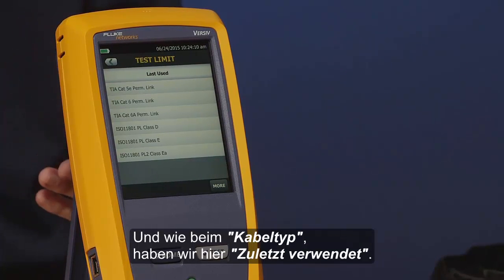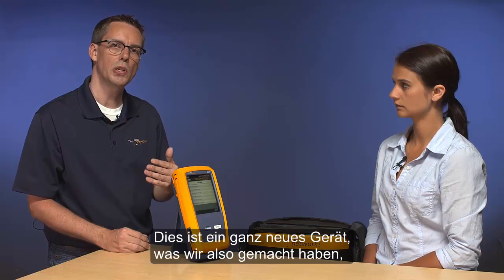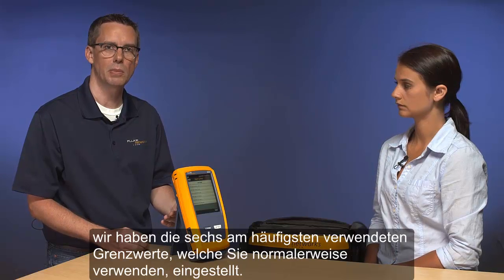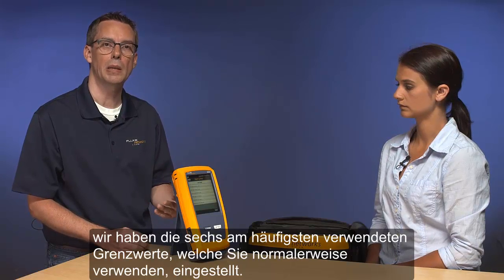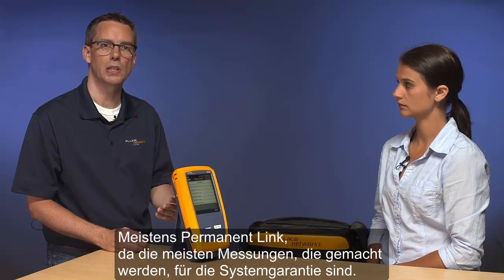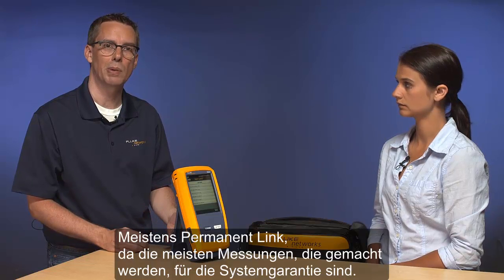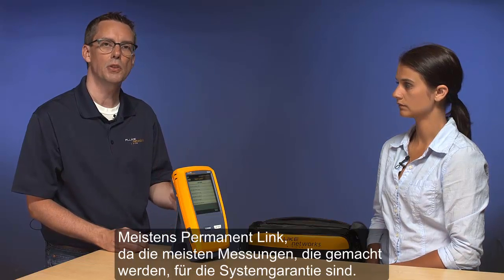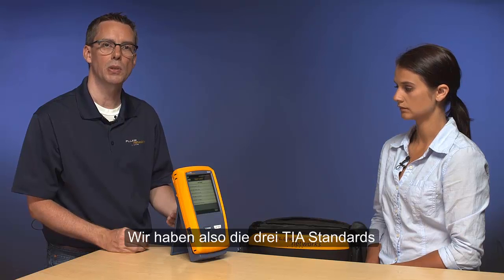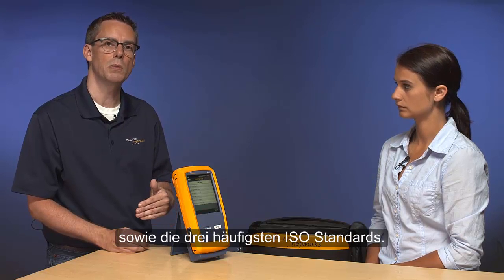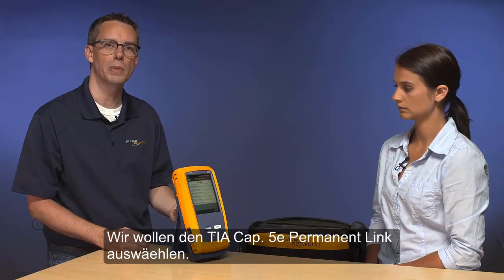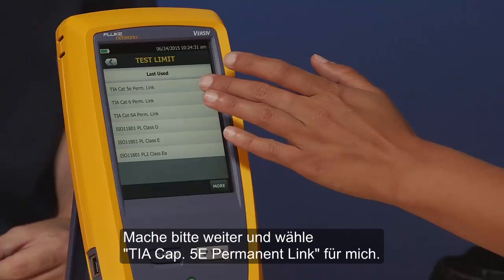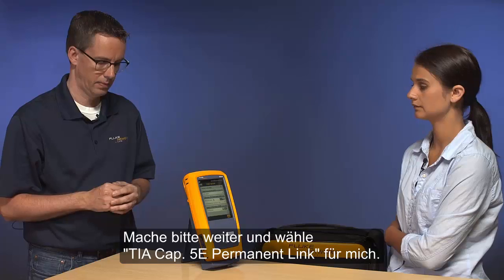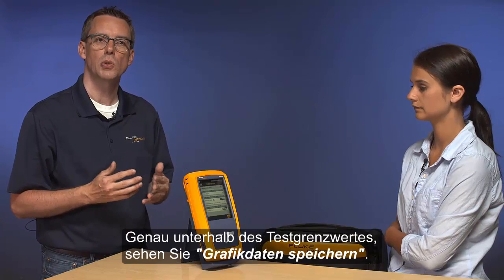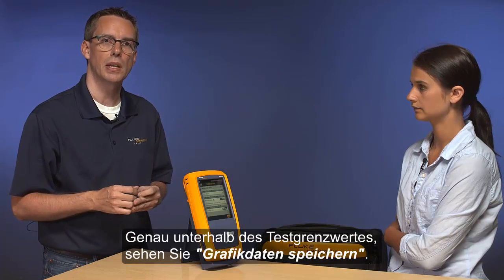This is a brand new instrument, so what we've done here is we've put up the 6 most common test limits that you typically come across, mainly permanent link, because most of the testing is being done for warranty applications. So we have the 3 TIA standards and we have the 3 most common ISO standards. We're going to be selecting TIA Cat 5e permanent link, so go ahead and select TIA Cat 5e permanent link for me. So just below the test limit, you'll see store plot data, and we're going to leave that on.